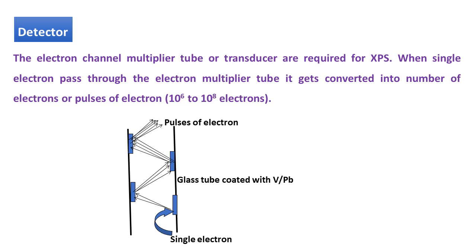The detector. In XPS, detector is electron channel multiplier tube or transducer. When a single electron passes through the electron channel multiplier tube, it gets converted into number of electrons or pulses of electrons, that is 10 to the 6, 10 to the 8 electrons. Here you can see in the diagram: when single electron passes through the glass tube which is coated with vanadium and lead metal atom, when single electron passes through the electron channel multiplier tube, it gets converted into number of electrons or pulses of electrons, that is 10 to the 6 to 10 to the 8 electrons.